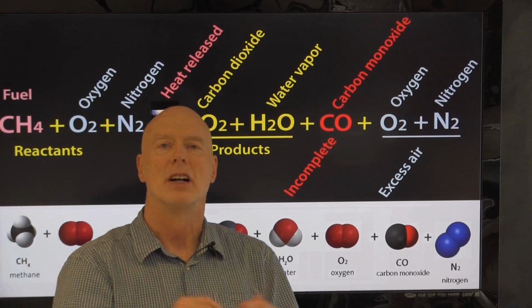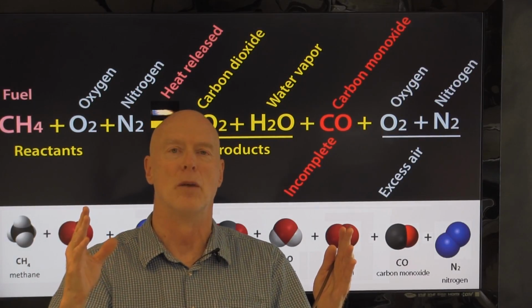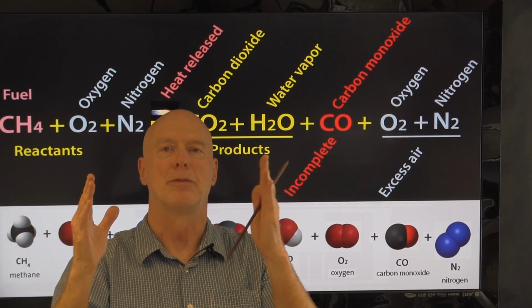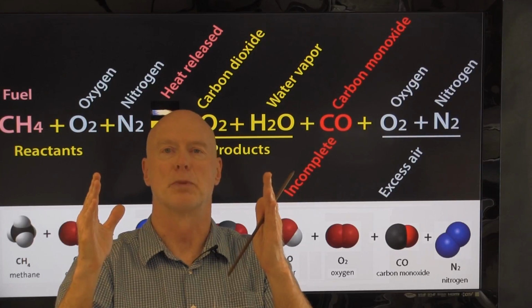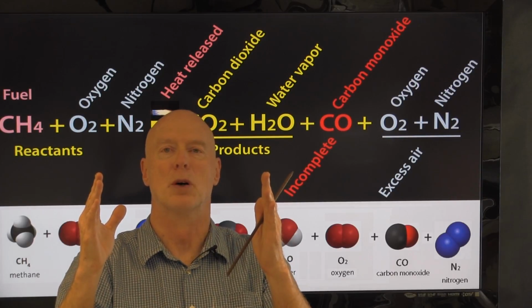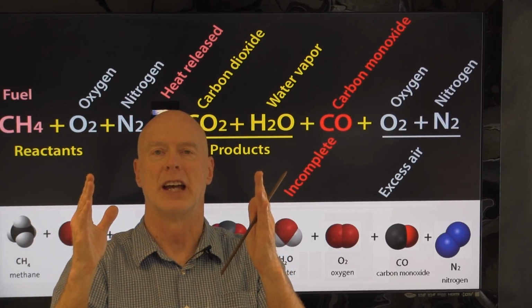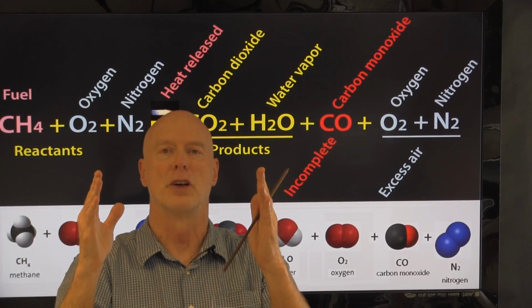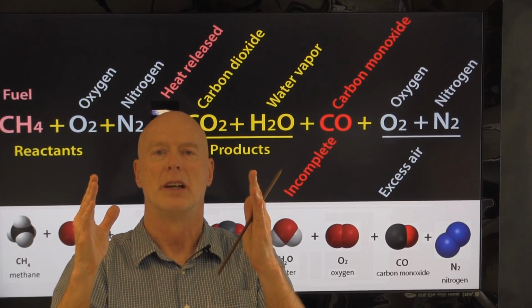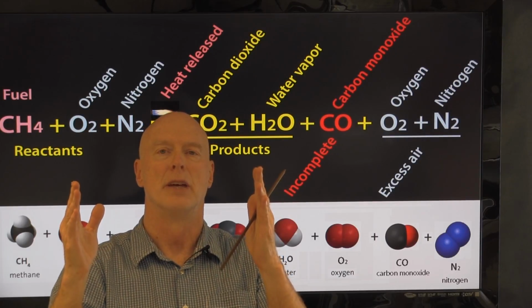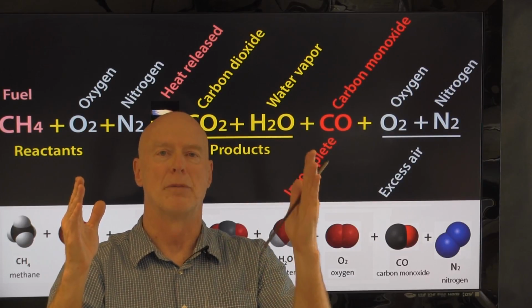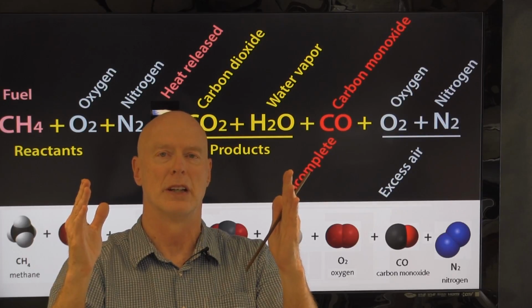And you have kind of a spec that goes from all the way down to 50 parts per million up to 200 parts per million would be acceptable under a lot of different standards. Where if it was air-free, it would be a larger measurement. And it would go from maybe 100 parts per million all the way up to 400 parts per million.